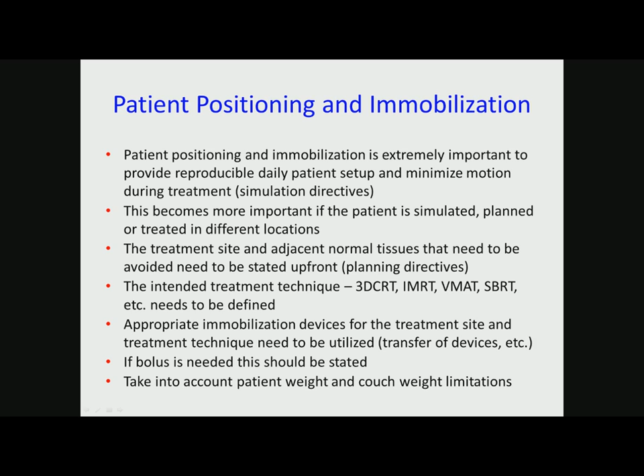Patient couch weight has become a problem now because we have different couches, like ExacTrac couches have a lower weight limit, and so the simulating therapist needs to know that up front so that when they put the patient on a schedule, they know the weight of the patient and the limitations of each couch. TrueBeam couches have a different limit, the old Varian couch has a different limit, Elekta has a different limit. So you need to have all that up front at the simulation stage.